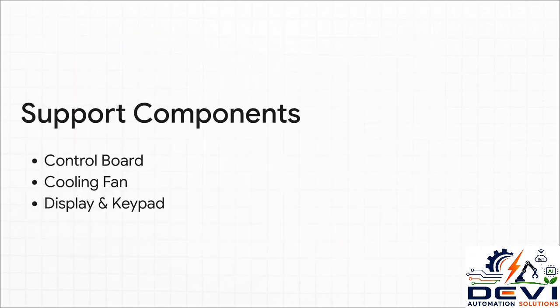But those power components can't just operate in a vacuum. They need an essential support system. So you've got the control board, basically the brain of the VFD, processing all the logic and sending signals down to the IGBTs. Then you have the cooling fan; all that high-speed electrical switching generates a ton of heat, so temperature management is vital. And finally, the display and keypad, the human-machine interface that allows technicians and engineers to program parameters, monitor performance, and troubleshoot faults right there on the factory floor.